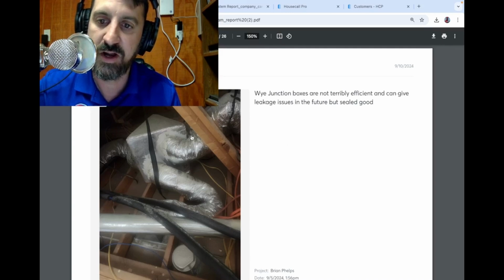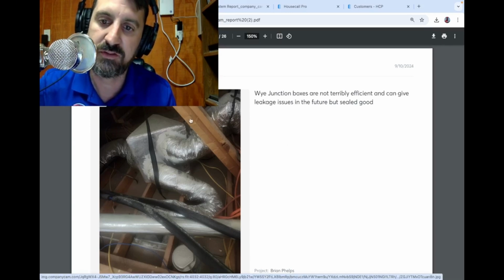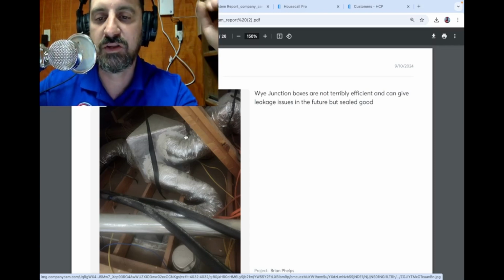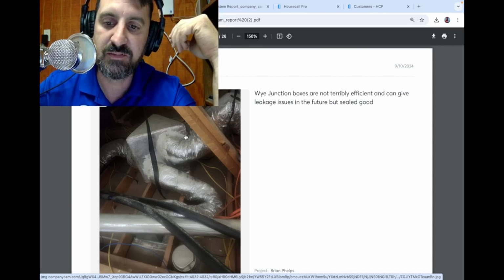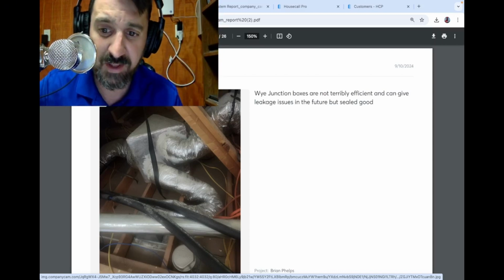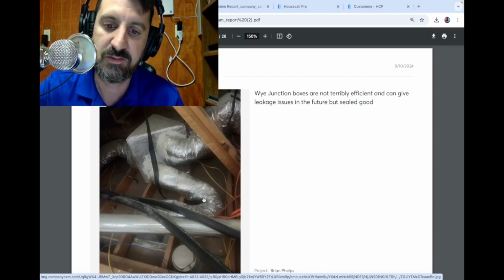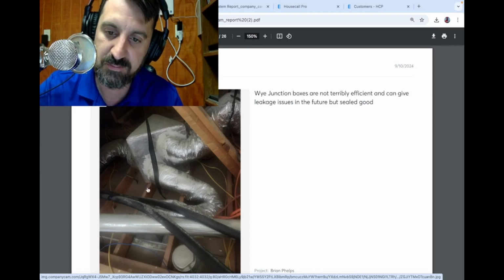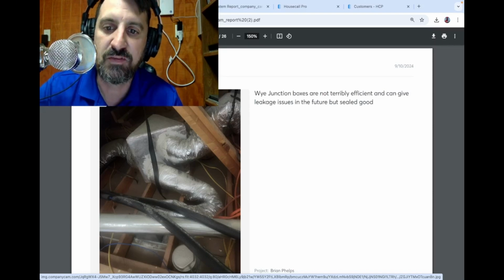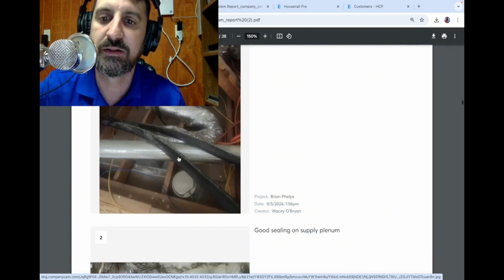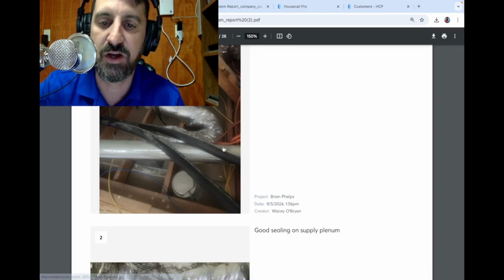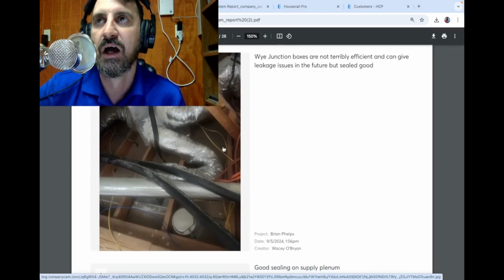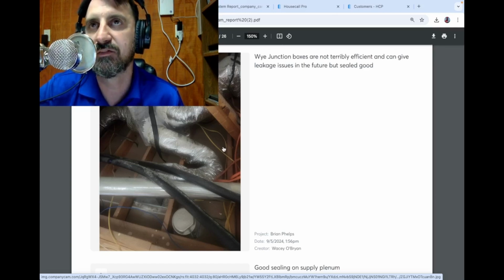I don't like these triangular Y junction boxes. What we typically see is these seams up here on the triangle on the top will essentially break down over time, and you'll see leakage in them. This one has a hanger for it, but they cut the hanger for some reason. So you can see the kinks in the ductwork, and then this duct swoops out and over and up. It's cool. You can see they sealed the crap out of it. They put a bunch of mastic on it. But anyways, I'm not a fan of these triangular boxes. I prefer either Ys or straight runs. I personally only Y a duct if it's going to the same room.